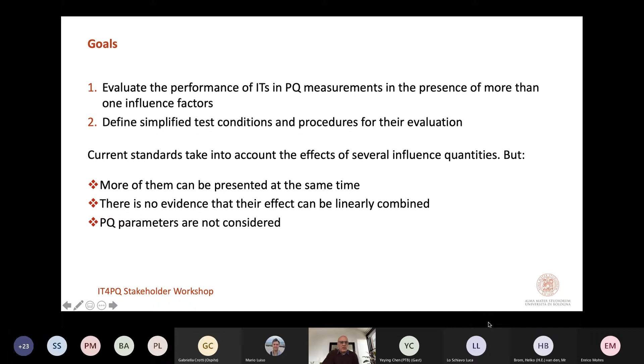The reason for this goal is that the current standard, as probably everybody knows, does not take into account this aspect. In particular, from the point of view of influence quantities, the current standard only considers the presence of one influence factor at a time, but of course, in actual situations, more than one can be present at the same time, and there is no evidence that the effects can be linearly combined. And mainly, power quality parameters are not considered, given that the standards only refer to the well-known ratio and phase errors. This is the reason for which Work Package 3 wants to reach as a final result the goals shown in this slide.